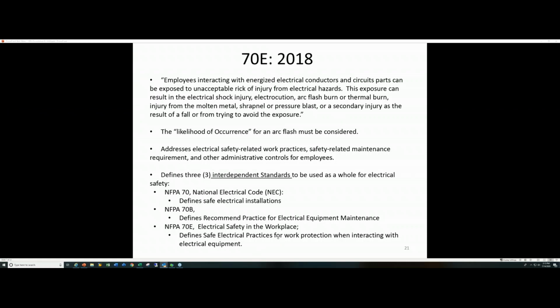NFPA 70E is the third standard that covers electrical safety in the workplace. It defines the practices. How is the electrician, the electrical engineer, to be protected? What are some of the things he can do to stay out of the line of fire, to stay at least safe where he's not getting anything more than a second-degree burn should something terrible happen? How do you do that? And what are the policies and procedures and administrative requirements that have to happen?